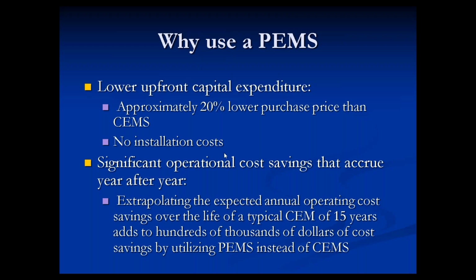Whereas with a CEMS, you're getting an electrical or mechanical contractor to physically install the system, run wires, run utilities such as power and air. Very minimal such costs exist with a PEMS because you've simply got a PC and then the comms wiring between it and perhaps the plant control system. Beyond the upfront cost savings, where the real cost savings occurs is the operational costs. And that is accruing year after year after year.